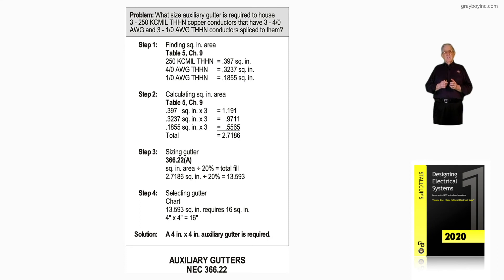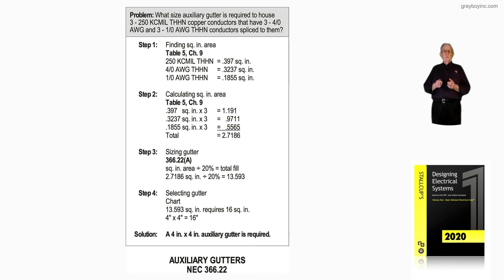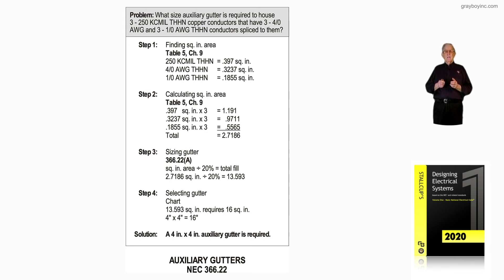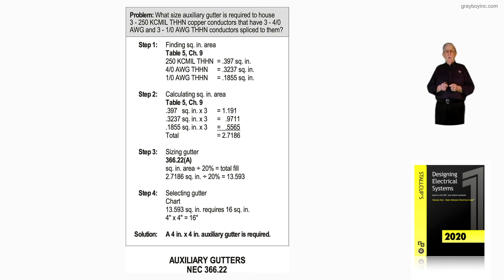Step three, we size the gutter. We're using the 20% rule, just dividing it in like we did in the quick calc — we divide 20% into 2.7186 and we come up with 13.593 square inches.